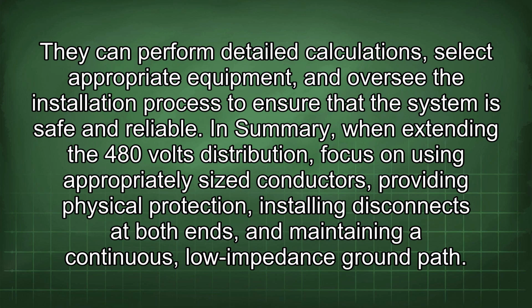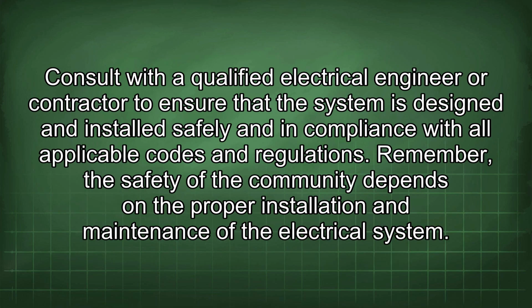and reliable. In summary, when extending the 480 volts distribution, focus on using appropriately sized conductors, providing physical protection, installing disconnects at both ends, and maintaining a continuous, low-impedance ground path. Consult with a qualified electrical engineer or contractor to ensure that the system is designed and installed safely and in compliance with all applicable codes and regulations. Remember, the safety of the community depends on the proper installation and maintenance of the electrical system.